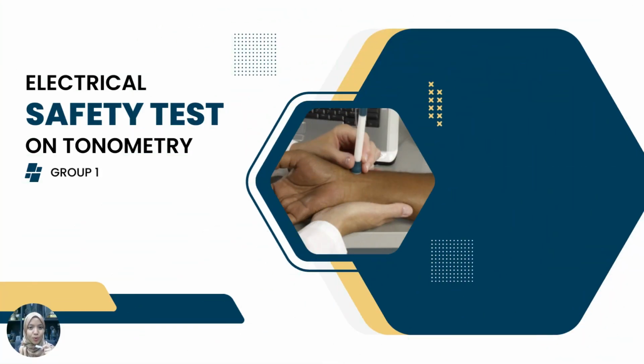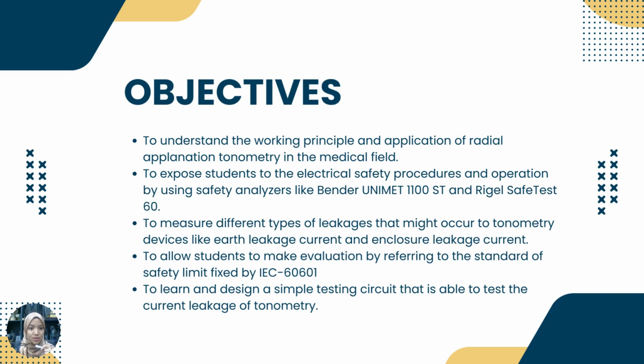Hi and Assalamualaikum. I am Sifatu Farzana. We'll be presenting on the objective part. First, to understand the working principle and application of radial applanation tonometry. Second, to expose students to the electrical safety procedure and operation. Third, to measure different types of leakages that might occur in tonometry. Fourth, to allow students to make evaluation referring to the standard IEC 60601-1 and to learn and design a simple testing circuit that is able to test the current leakage.